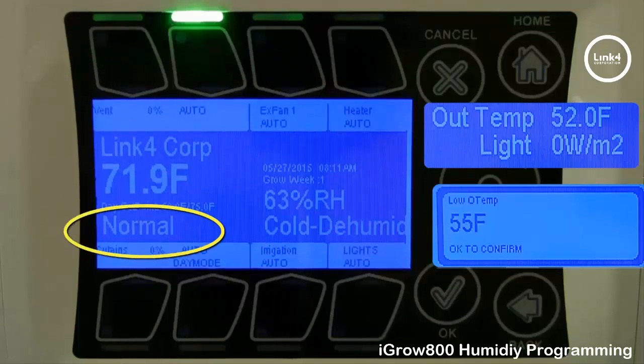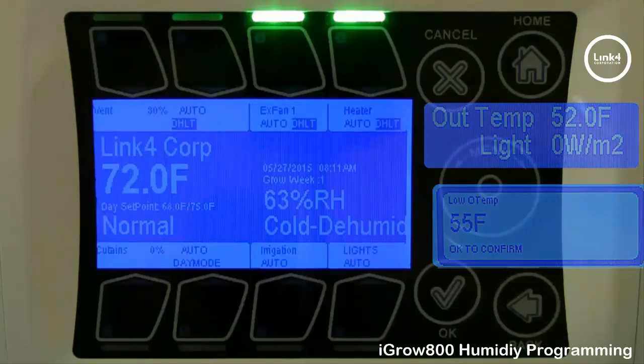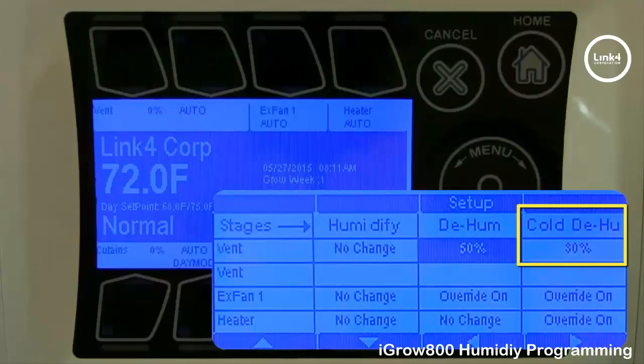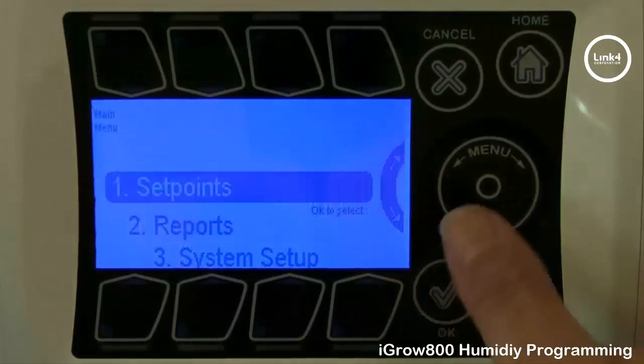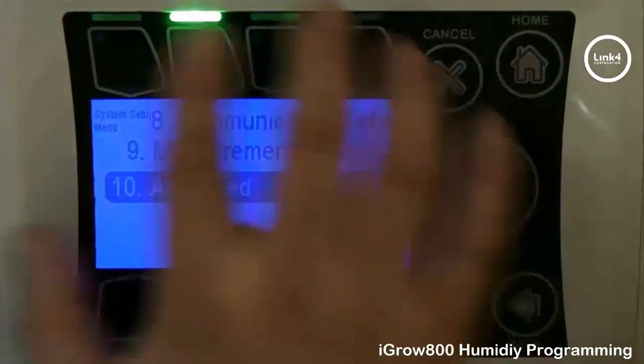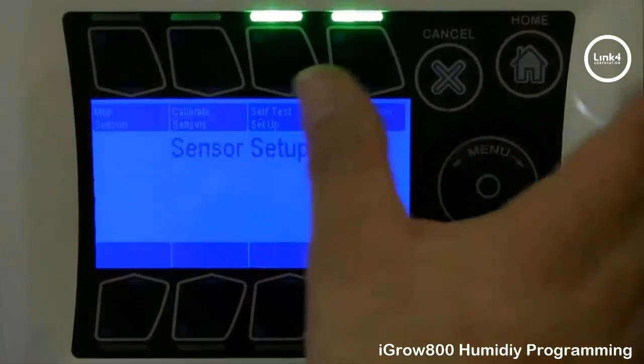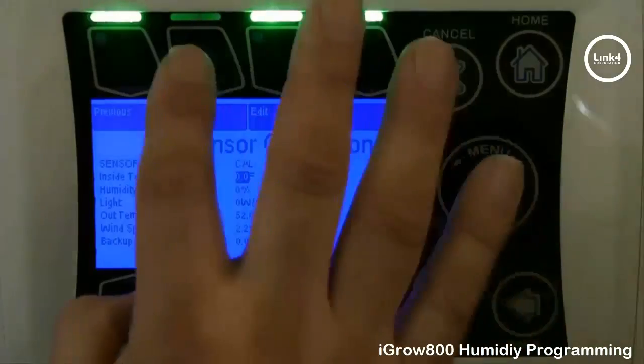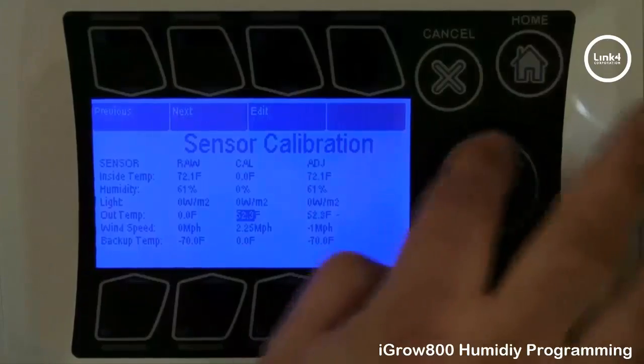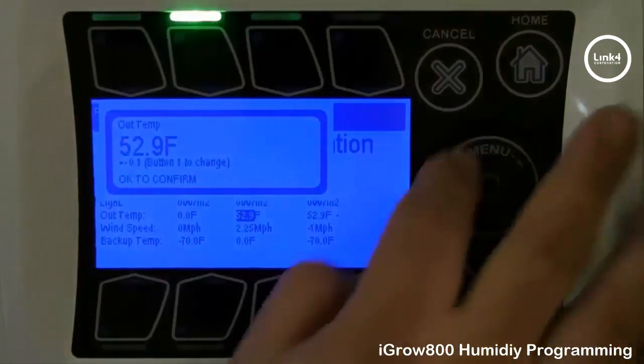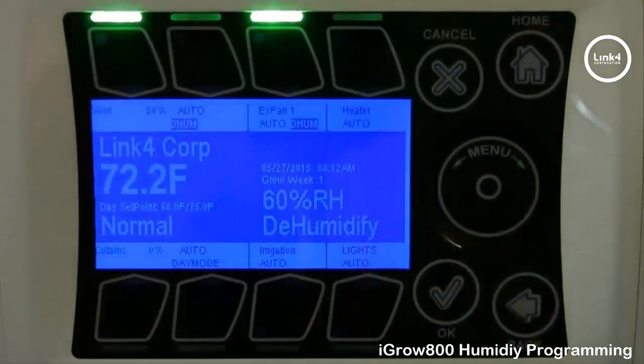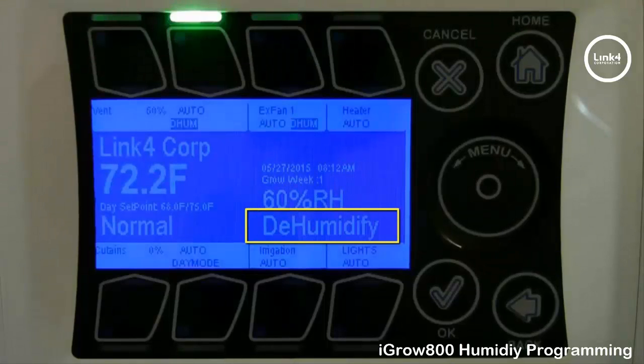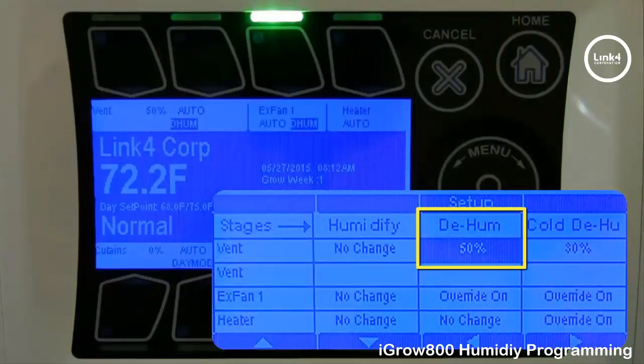Since we're in the normal state in cooling, you can see the vent cycling to 30% because in cold dehumidification our parameters were 30%, and the vents are cycling to 30% and then returning back to zero. This is a quick response because of our cycling time, but in normal circumstances you would make a larger cycle time period. Next, we'll hit OK, go to system setup, go to sensor setup, and calibrate our out temp to a greater value to force the controller into regular humidity. After making this change, hit home, save, and as you can see the controller immediately went into dehumidify. The vent percentage is now at 50 instead of 30, and the heater is no longer running because we're in regular dehumidification.